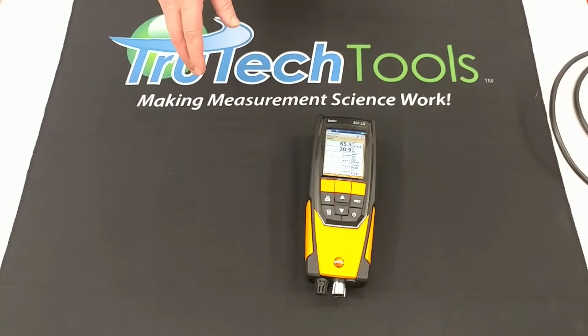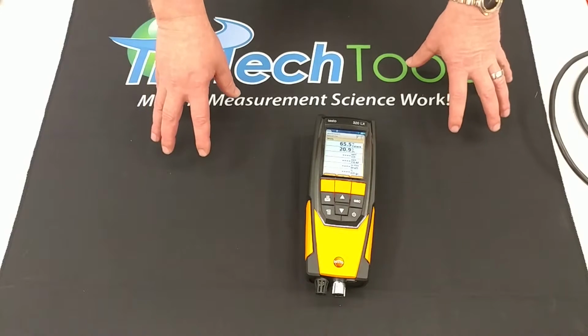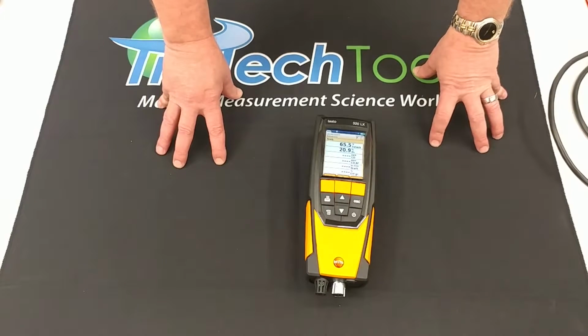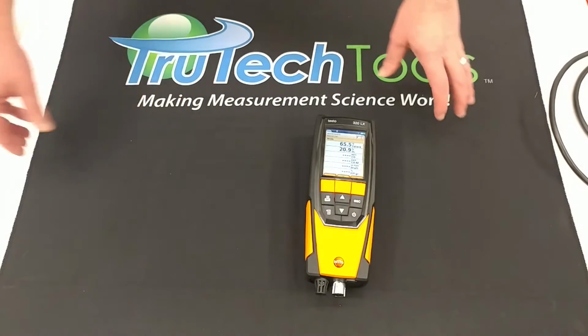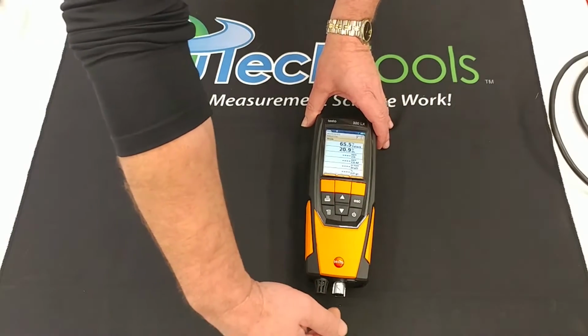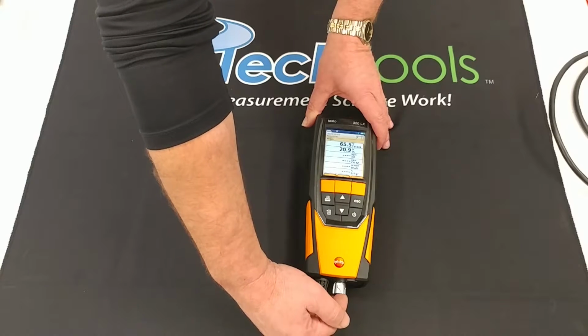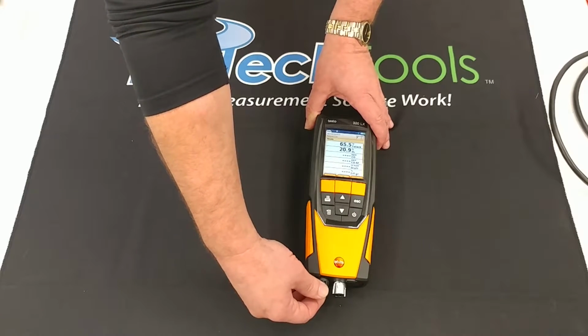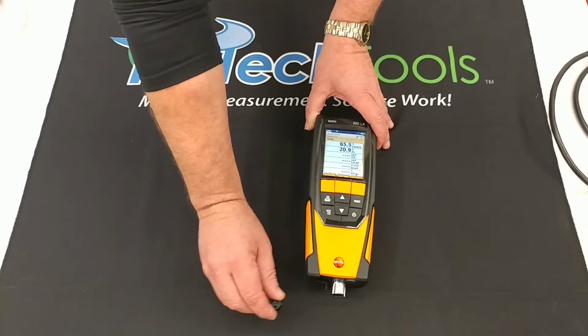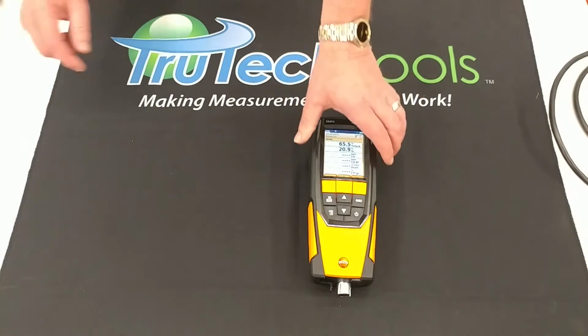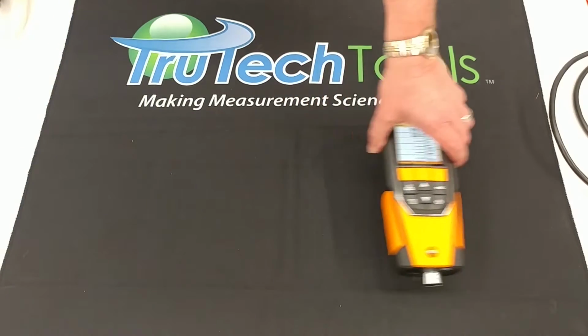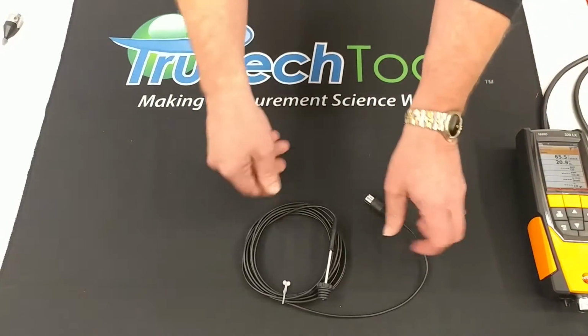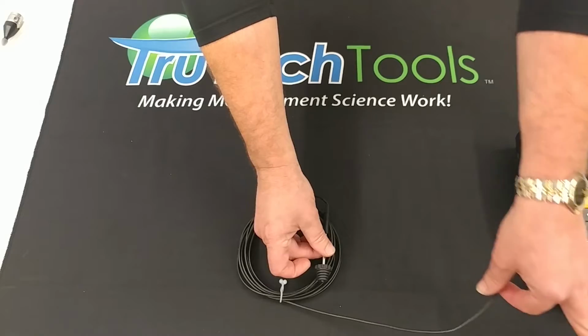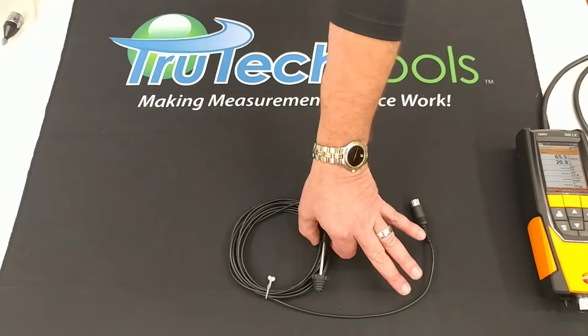The next thing I want to talk about on the Testo 320 is that it has the ability to be used with a bunch of different probe assemblies that they make. Some of the probe assemblies are going to plug into where the probe assembly is. Some of them are going to plug in when we remove the ambient air temp piece. The first one that is very popular is the combustion air temperature probe. So again, this plugs into the ambient air temp spot.